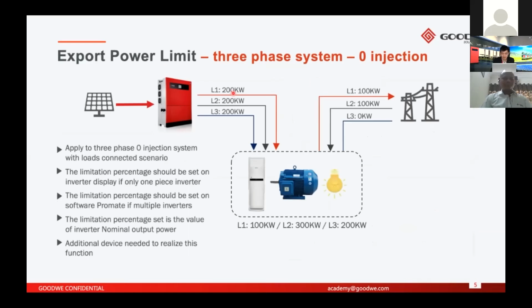And here is the three-phase case. It's also export power limit, a three-phase system with zero injection. Zero injection means 0 watt to the grid. In this case, phase 1 is 100 kilowatt consumption, phase 2 is 300 kilowatt consumption, and phase 3 is 200 kilowatt consumption. So the total consumption is about 600 kilowatt. The inverter will output 200 kilowatt on each phase to supply power to the loads.